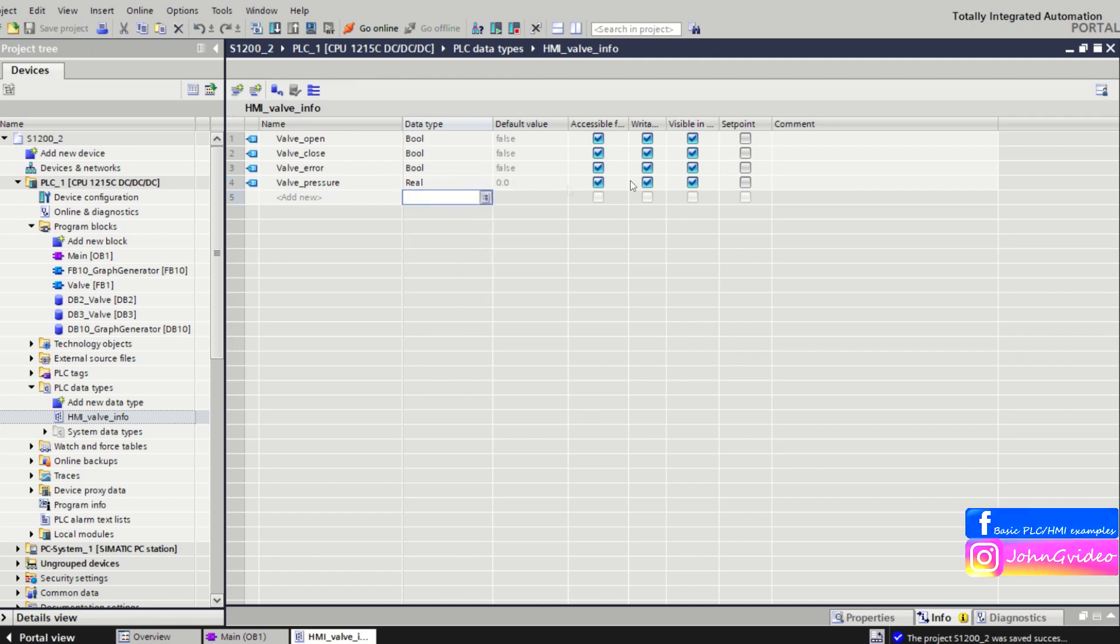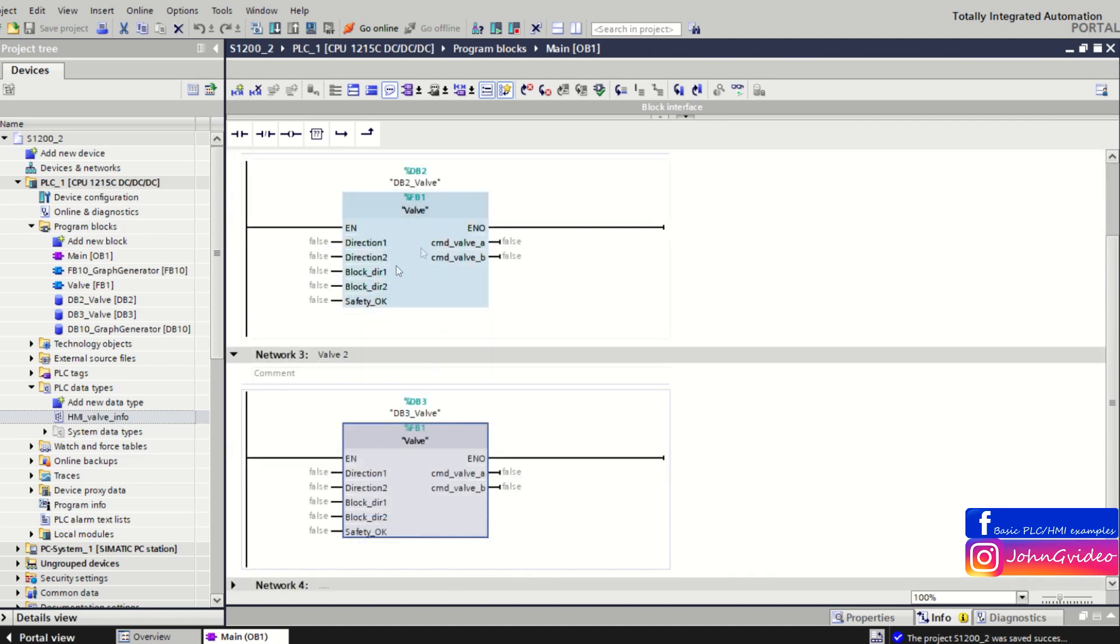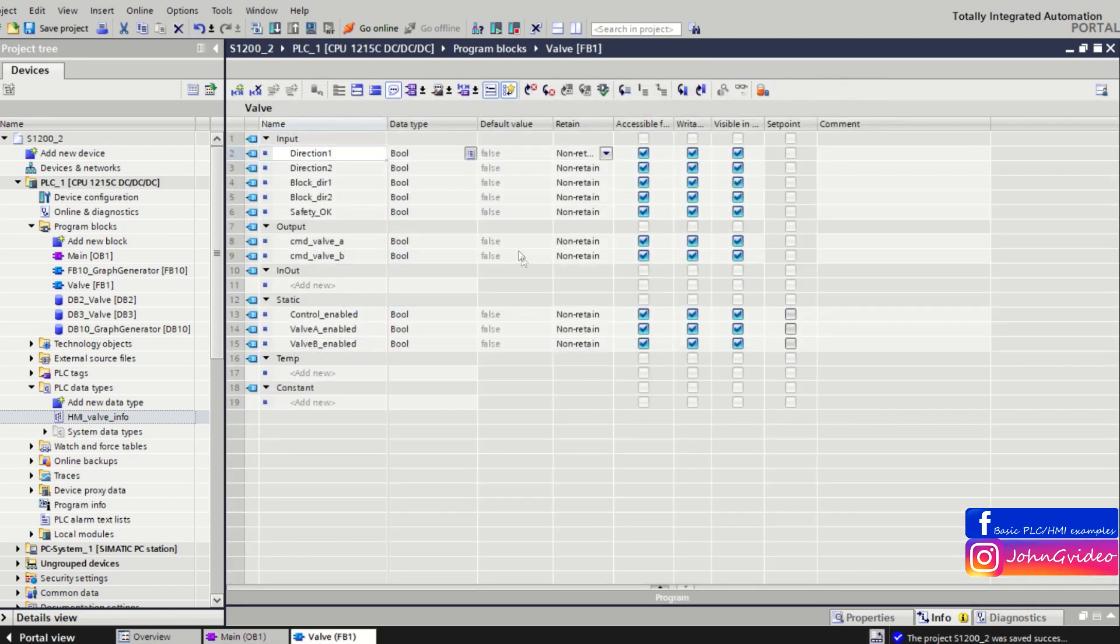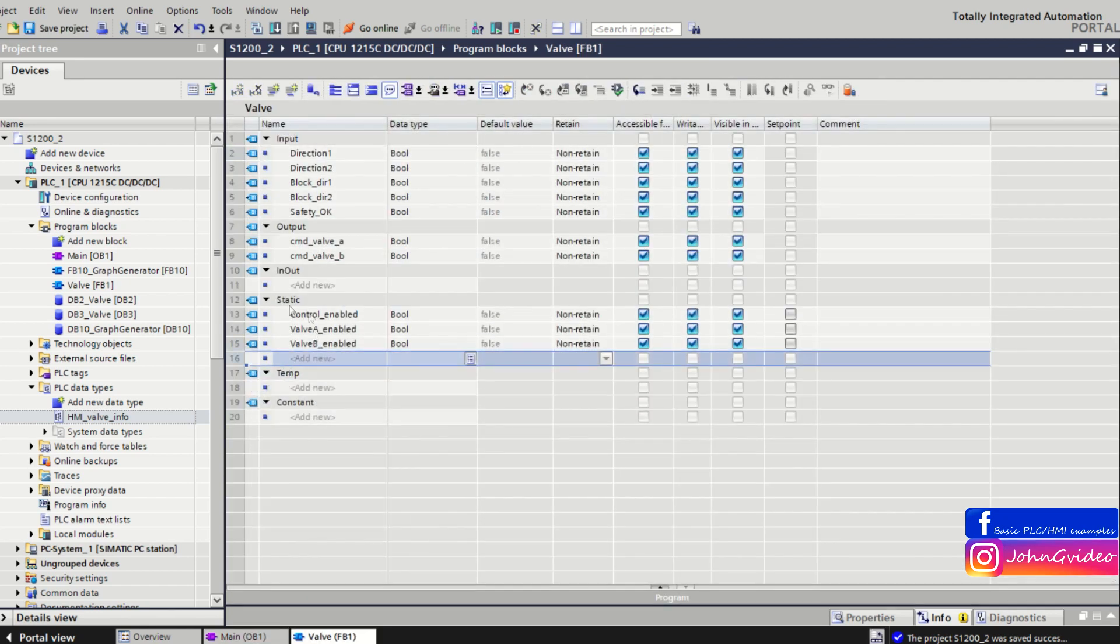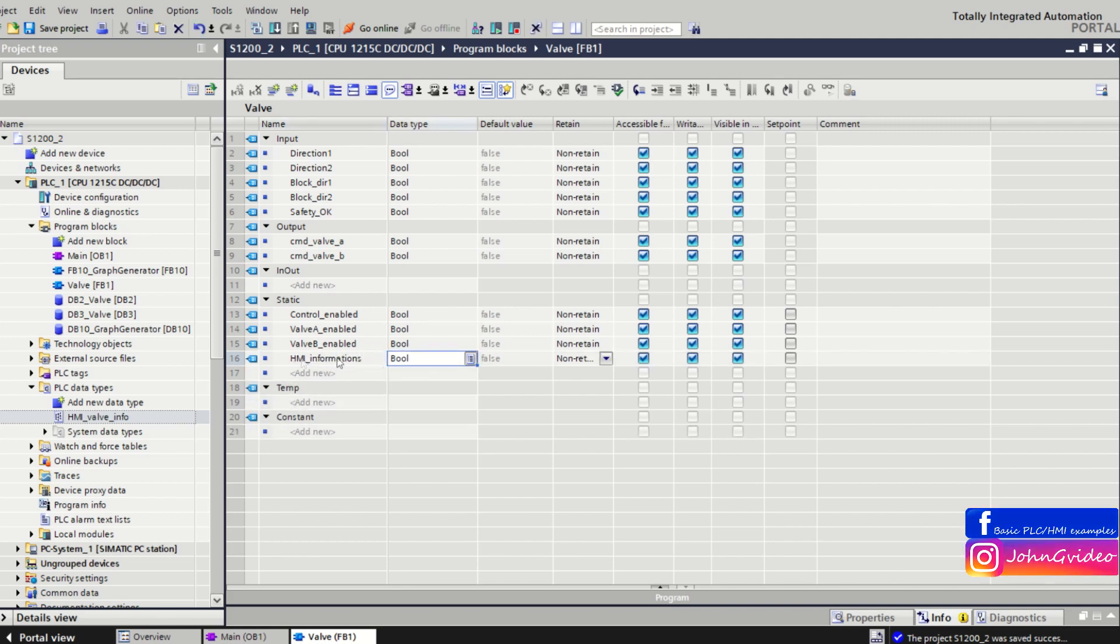We save the changes and now this is how we create the PLC data type. Now we can use this data type, for example, in valve function block. We open the block and we go to the static variables of the data block. Here we create variable HMI informations and the data type of this variable will be HMI valve info data type.